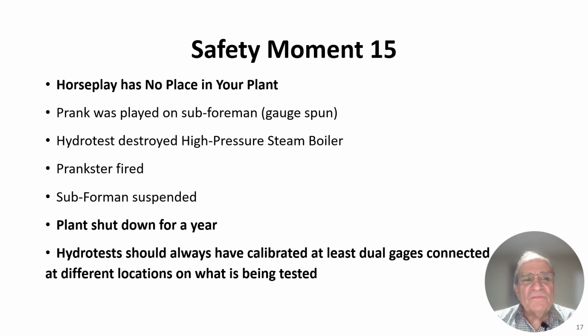Safety moment number 15. Horseplay has no place in your plant. A prank was played on a sub-foreman. Somebody spun the gauge on him. The sub-foreman was doing a high-pressure boiler hydro test, and it was going to be a test at 1500 psi. So he used a 2000 psi pressure gauge to do the test. Somebody pranked him and spun the gauge so that when the gauge was reading 0, it was really up to 2000 psi.